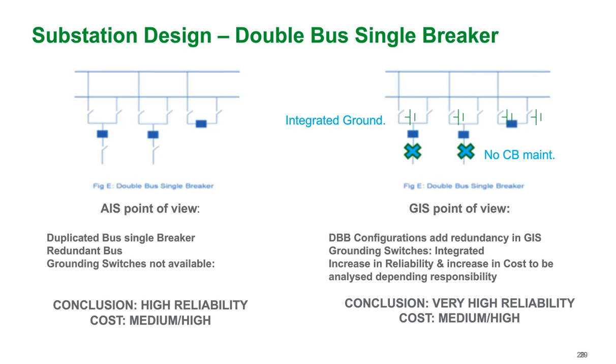And then on the GIS side, you get extremely high reliability with this type of arrangement because you have a secondary bus, another bus that you can pull from. In the unlikely event that you did have an issue and you did have to shut down one bus, you still have another source and you can maintain your uptime at your facility. So this has an extremely high reliability, but the cost of this configuration is also quite high.